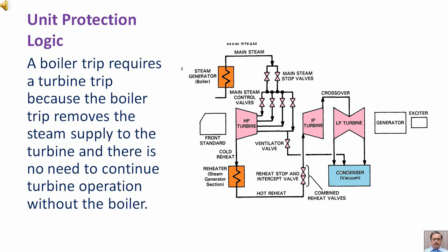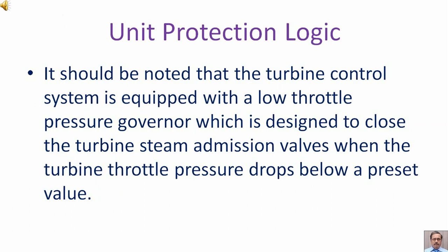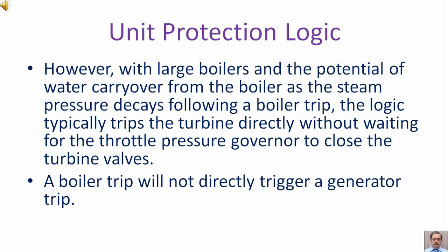A boiler trip requires a turbine trip because the boiler trip removes the steam supply to the turbine and there is no need to continue turbine operation without the boiler. It should be noted that the turbine control system is equipped with a low throttle pressure governor, designed to close the turbine steam admission valves when the throttle pressure drops below a preset value. However, with large boilers and the potential of water carry-over as steam pressure decays following a boiler trip, the logic typically trips the turbine directly without waiting for the throttle pressure governor. A boiler trip will not directly trigger a generator trip.